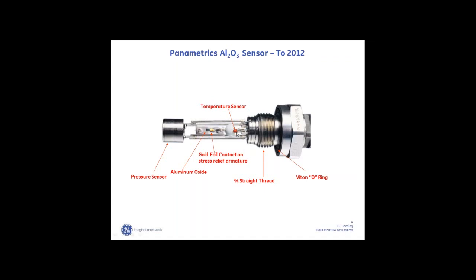We can also couple that sensor with a temperature sensor. Temperature is needed to measure derived parameters from the fundamental moisture measured in dew point. Pressure is also needed to convert to parts per million by volume — we measure the dew point, which gives us the partial pressure of water, and if we divide that by the total pressure we get the volume ratio. So the two parameters we see most often in trace moisture are dew point and parts per million by volume.